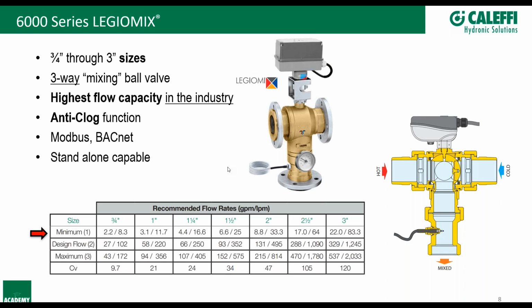That's a great question. Designers and mechanical contractors are probably used to the idea of having multiple storage tanks or multiple heat sources. What you use in those scenarios is similar to what you'd use with multiple valves: either equal distance piping, where you get the same head loss or pressure loss through each side, guaranteeing equal flow, or some form of reverse return piping, first in last out, last in first out. I've got some blanket type diagrams that are pretty neat. You want to make sure you're getting equal flow, but even if it's not exact, as long as it's pretty close, the valves will still function properly and you'll probably be okay.